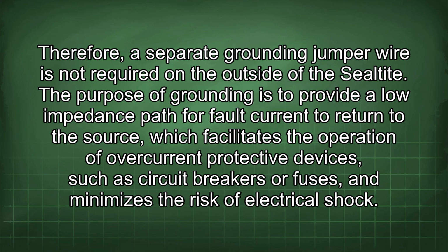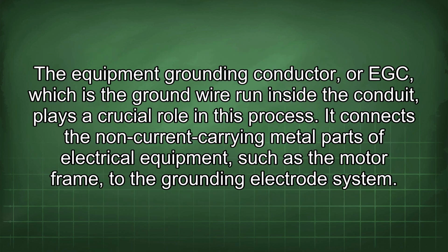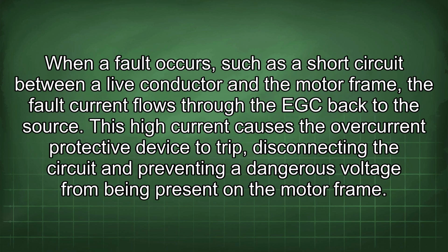The purpose of grounding is to provide a low impedance path for fault current to return to the source, which facilitates the operation of overcurrent protective devices, such as circuit breakers or fuses, and minimizes the risk of electrical shock. The equipment grounding conductor, or EGC, which is the ground wire run inside the conduit, plays a crucial role in this process. It connects the non-current carrying metal parts of electrical equipment, such as the motor frame, to the grounding electrode system. When a fault occurs, such as a short circuit between a live conductor and the motor frame, the fault current flows through the EGC back to the source. This high current causes the overcurrent protective device to trip, disconnecting the circuit and preventing a dangerous voltage from being present on the motor frame.